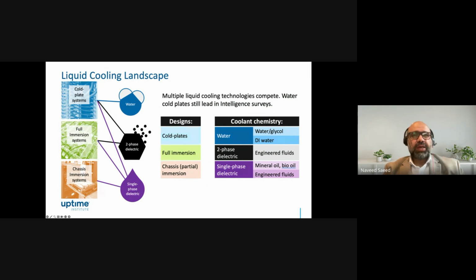And I think for chassis and partial immersion, it's mostly single-phase dielectric because it's impossible to seal that one, so the vapors cannot be contained. So it's single-phase dielectric fluid. If we look at water, it's a water-glycol mix or deionized water. For two-phase, these are engineered fluids, and there are some concerns around the safety of these fluids because they have forever chemicals, and this needs to be looked after when you are trying to adopt a two-phase dielectric fluid. Single-phase fluids are usually mineral-based or bio oil, and they can be engineered as well, but they are considered safer than two-phase dielectric fluids in adoption.